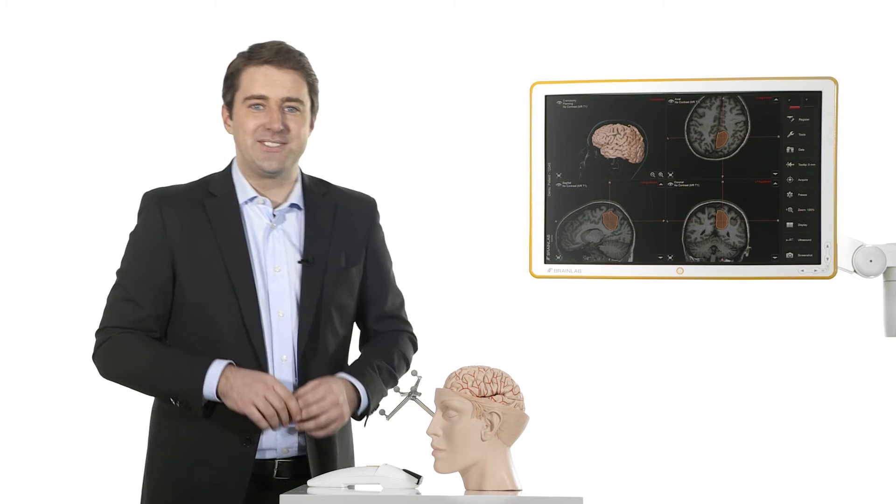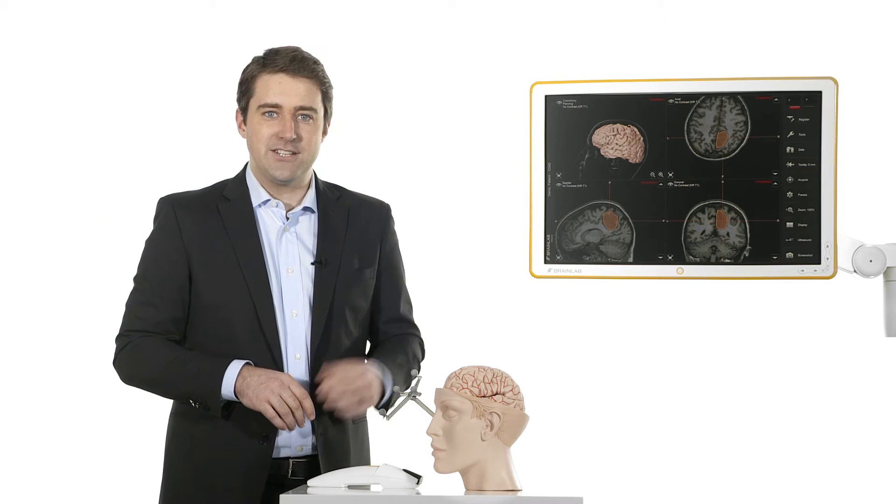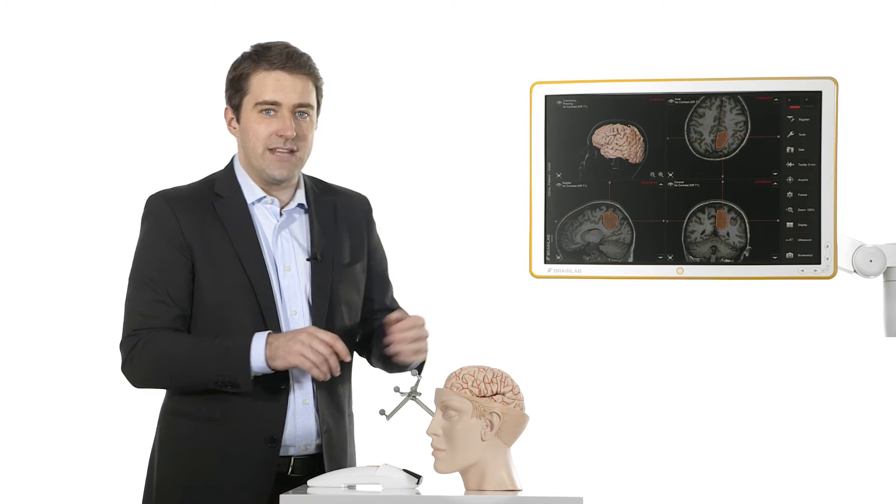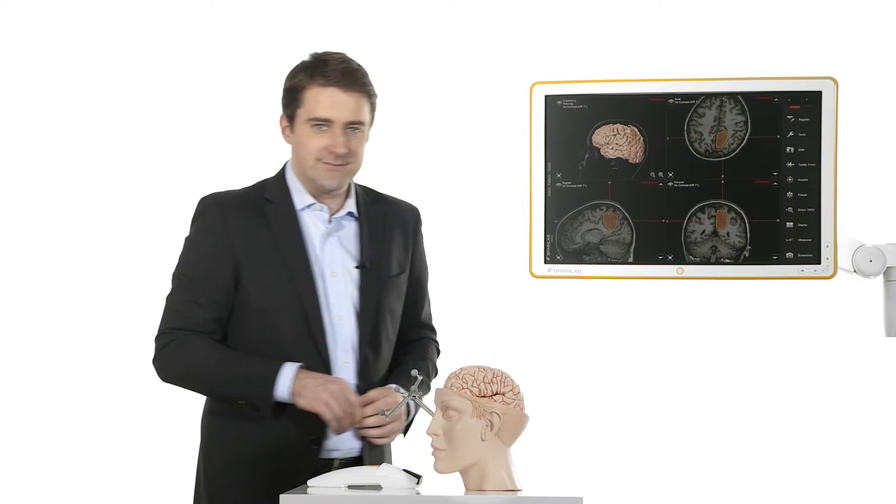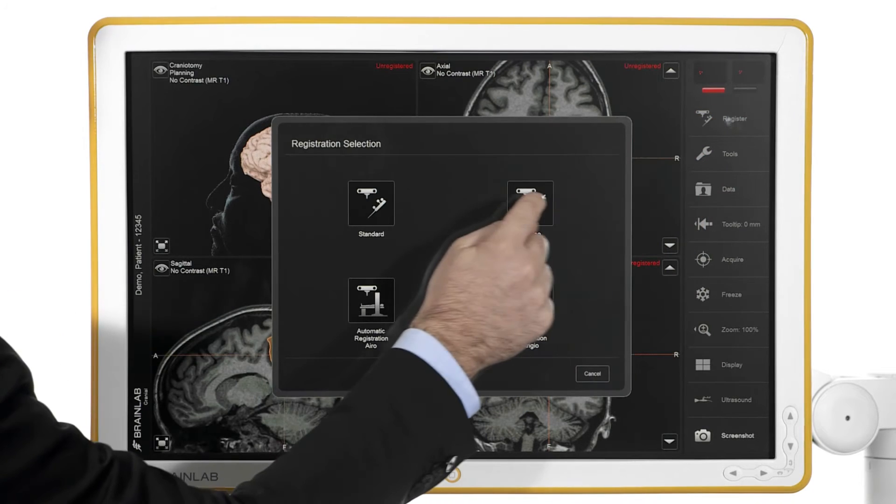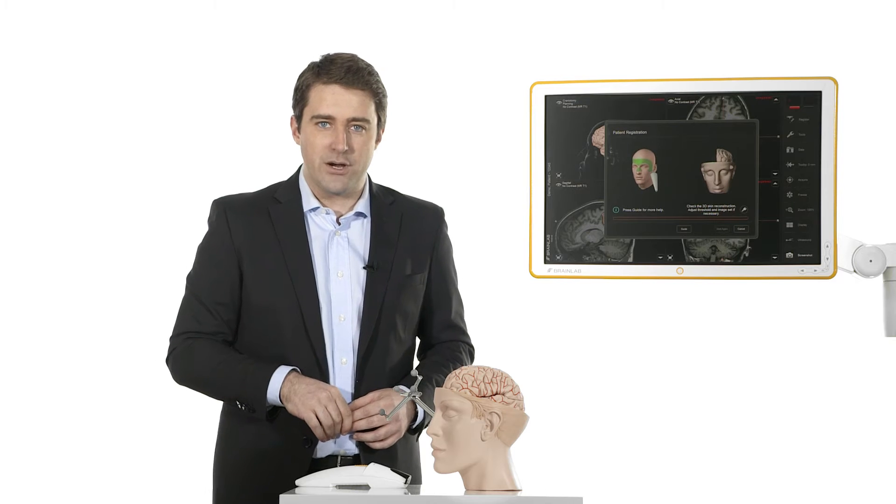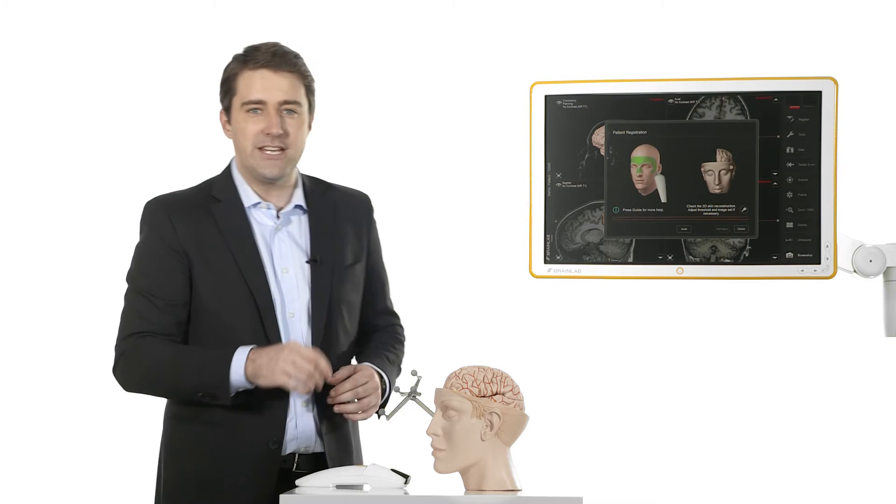Registration is a critical step for navigation as it links the patient's actual position with their virtual anatomical data to enable accurate tool tracking. Surface matching is a registration technique in which multiple points are collected to provide the software with the surface shape of the patient.